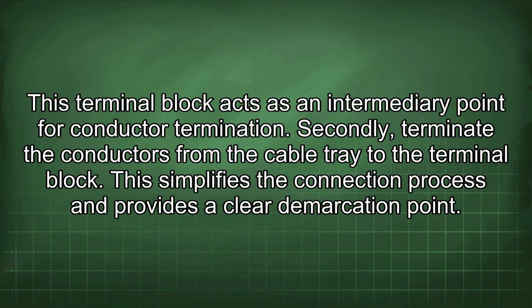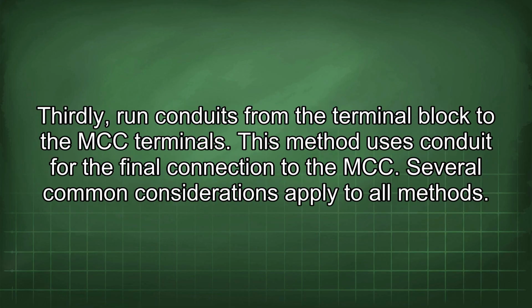This simplifies the connection process and provides a clear demarcation point. Thirdly, run conduits from the terminal block to the MCC terminals. This method uses conduit for the final connection to the MCC. Several common considerations apply to all methods.